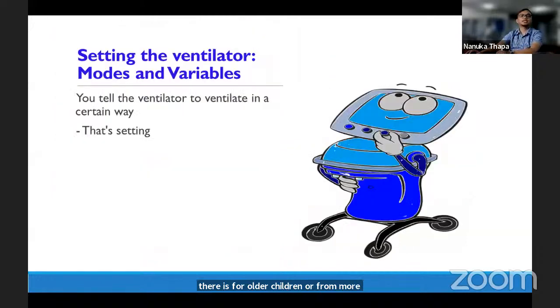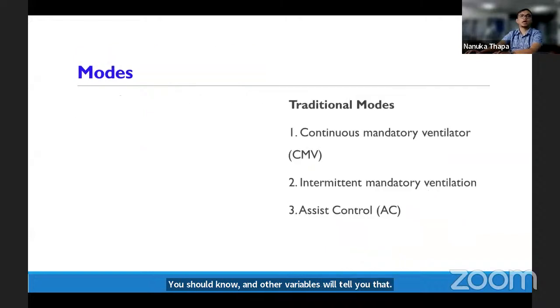How to do settings in a ventilator? There are different modes you should know, and other variables will tell you that when we go forward, how to ventilate in certain ways. We have two modes. One is traditional modes and one is newer modes. In traditional modes, like when initially mechanical ventilation was invented, we got only three. That is continuous mandatory ventilator, also called as CMV, intermittent mandatory ventilator, that is IMV, and assist control.